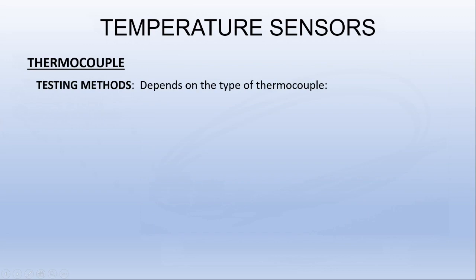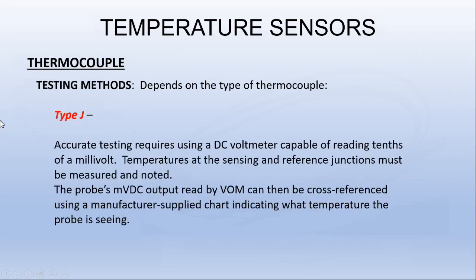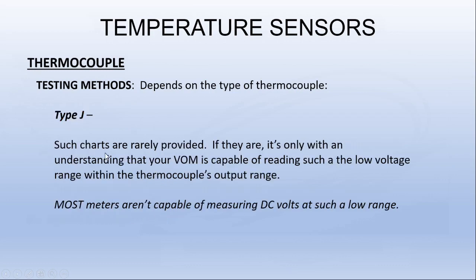Okay, for testing, it depends on the type of thermocouple. The type J, accurate testing requires using a DC voltmeter capable of reading tenths of a millivolt. Temperatures at the sensing and reference junctions must be measured and noted. The probe's millivolt DC output read by the voltmeter can then be cross-referenced using a manufacturer-supplied chart indicating what temperature the probe is seeing. Such charts are rarely provided. If they are, it's only with an understanding that your voltmeter is capable of reading such a low voltage range within the thermocouple's output range. Most meters aren't capable of measuring DC volts at such a low range.